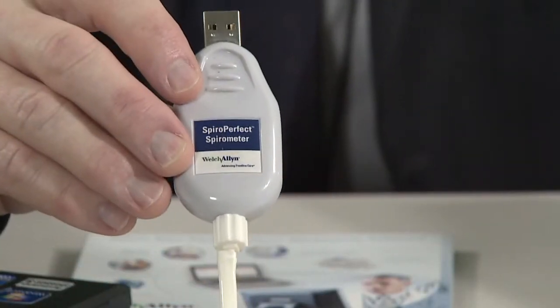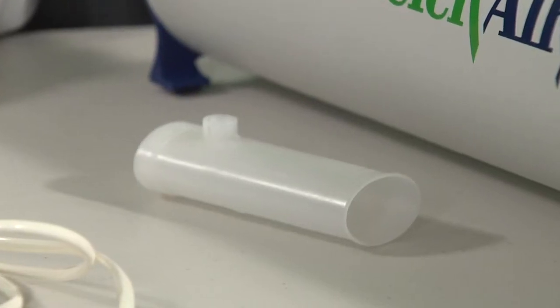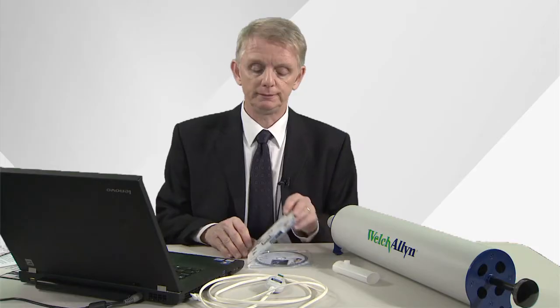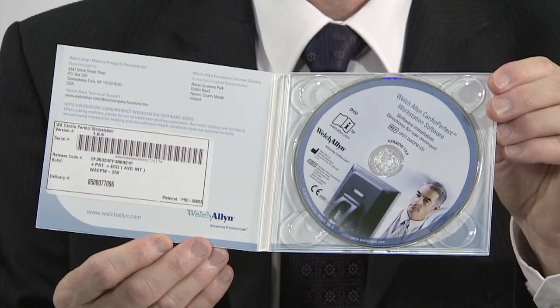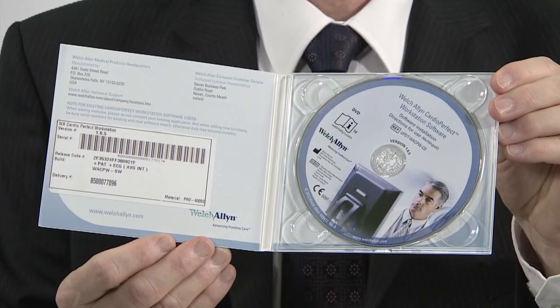When you buy the spirometer, you get a USB connection with tubing, disposable flow mouthpieces for the patient to use, CardioPerfect software, which should be loaded to your PC or laptop. Finally, there's a 3-litre calibration syringe, and you should calibrate your spirometer once at the start of each day of use. Now, taking a spirometry test using the CardioPerfect software is really easy.